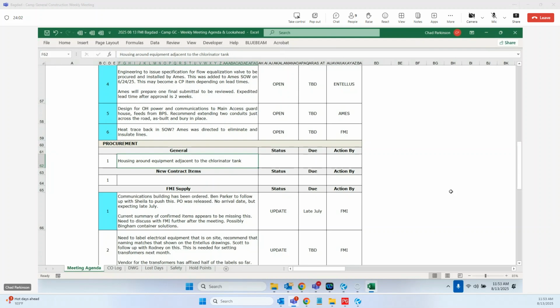So I just made a bigger enclosure to incorporate all that equipment. Is this where we can install the equipment on a unistrut rack and then set a building over it, or does it have to mount to the building? No, we don't need a building. All we need is it mounted on a unistrut, and I believe the detail shows that. Yes, you can mount it on unistrut and have it in a NEMA 4 cabinet that incorporates the analyzer and that piece of ancillary equipment it needs to operate.